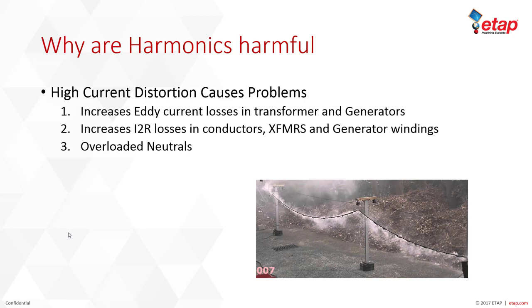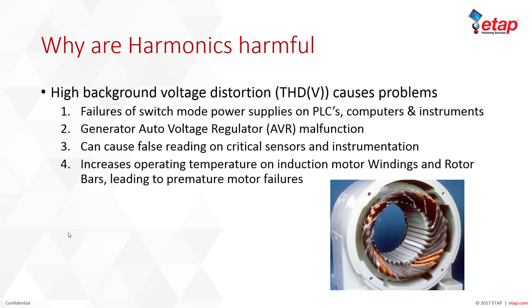Let's go over high current distortion and the problems it causes, and then we'll get into high voltage distortion. For high current distortion, it mainly increases eddy current losses in transformers and generators. It also increases resistance losses in conductors, transformer and generator windings, and can overload neutrals.